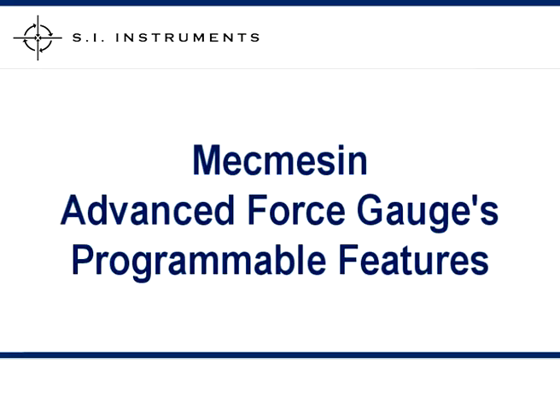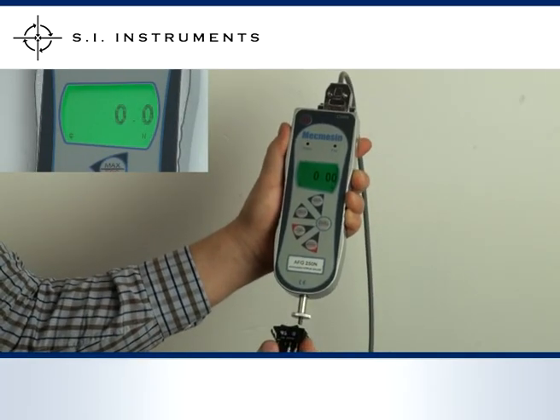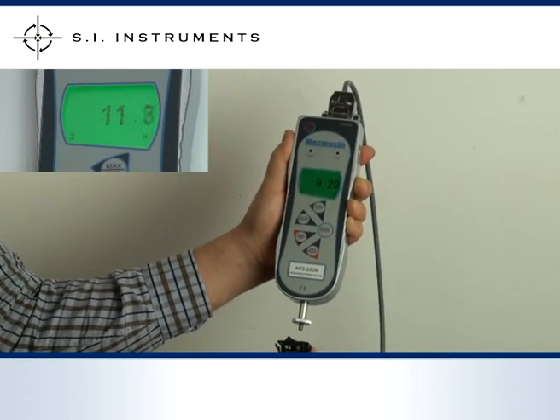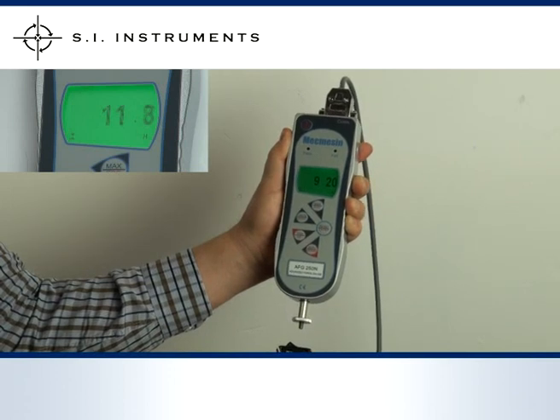The Mecmesin Advanced Force Gauge also has many advanced programmable features. When testing electrical switches, the peak force is not always the same force as when the switch is making or breaking contact. With the freeze reading feature, the gauge can be connected to the switch and will freeze the reading on the display when the switch makes or breaks electrical contact.